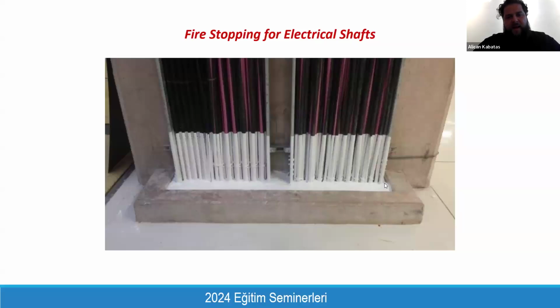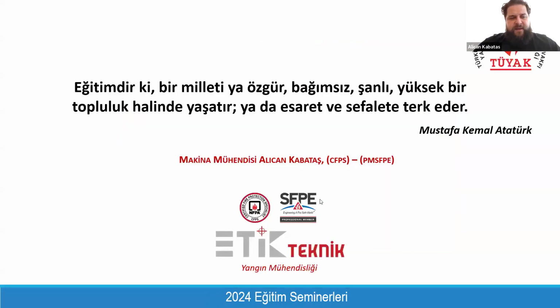interruption. And also, within the electrical rooms, you will have some electrical vertical opening, cable vertical shaft. And when the cable pulling is done at the end of the day, before commissioning of the building, all of these cable shafts should be filled by 2-hour fire-rated fire stopping material, so that the compartmentation integrity can be achieved. This was all that I would like to summarize you for architects regarding MEP point of view.